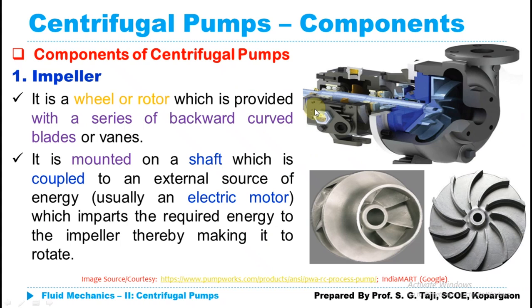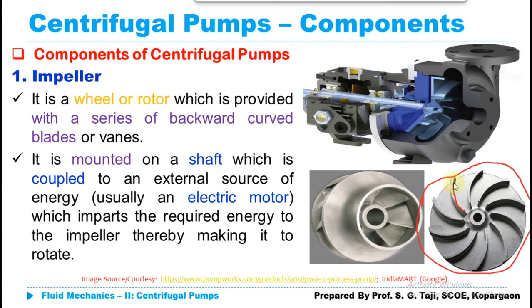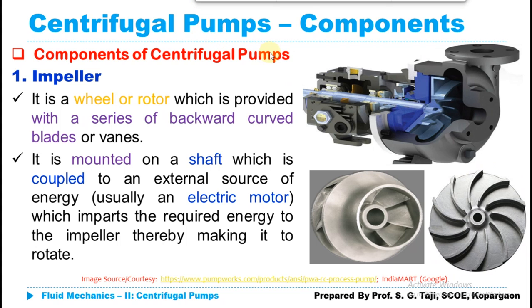The impeller is a wheel or rotor provided with a series of backward curved vanes. When it rotates, those backward curved vanes create angular momentum and exert force on the liquid in contact, developing centrifugal force. The impeller is mounted on a shaft connected to the electric motor, which converts electrical energy into mechanical energy transmitted through the shaft to the impeller. Based on design, impellers are classified as closed impeller, semi-open impeller, and open impeller.